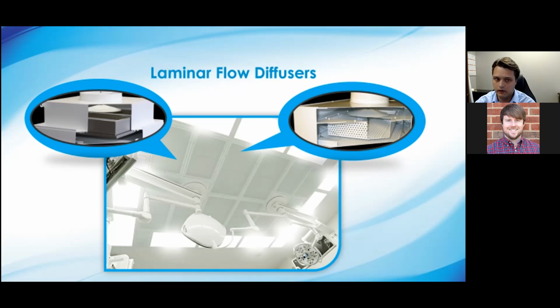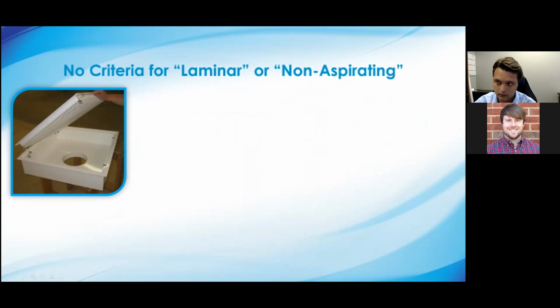One interesting note about the criteria for laminar flow diffusers is that ASHRAE 170, which is the code that governs operating room ventilation systems, defines devices that must be in the ceiling of an operating room as Group E non-aspirating, also known as laminar. Except there is no real criteria you need to test to in order to be called a laminar flow diffuser. Theoretically, anybody could go in their garage, make a device, and market it as a laminar flow diffuser. They could just make a metal box with a faceplate on it and call it a laminar flow diffuser. There is no actual test method that you need to meet, which gets important when you're writing spec language, because instead of having something with heavy baffling within it like this, you could end up with a diffuser that really is just a metal box with a faceplate on it.